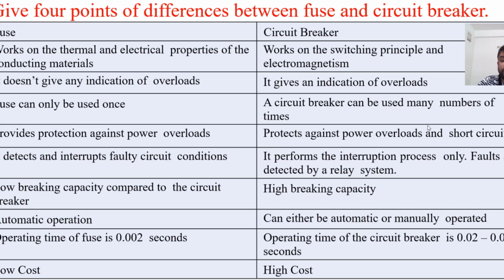Give any 4 points of differences between fuse and circuit breaker. Fuse works on thermal and electrical properties of the conducting materials, whereas circuit breaker works on switching principle and electromagnetism. Fuse does not give any indication of overloads, whereas breaker can give an indication of overload. Fuse can be used only once. Once it blows out, you cannot use it again, whereas in case of circuit breaker, you can use it many number of times.